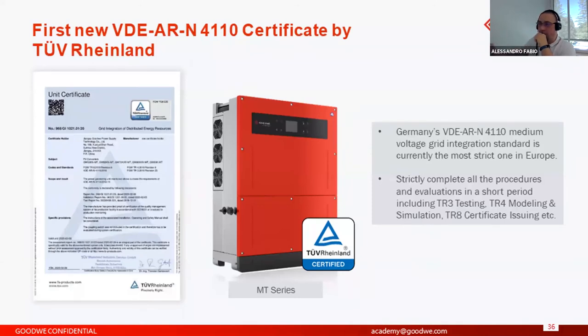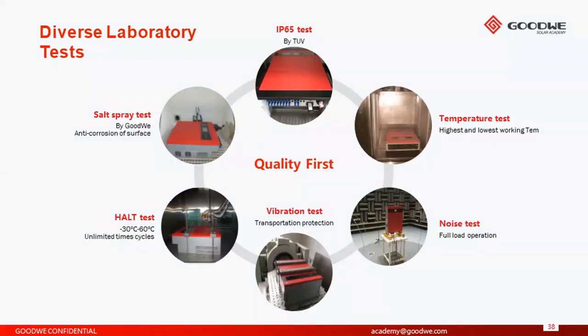So we also have certification worldwide, for example, a certificate for the German norms, the 4110 for the medium voltage, because it's a standard the German market requires. After production we have diverse laboratory tests inside. For example, the salt spray test or IP65 test for external devices. Internally we have our own tests: a temperature test, a noise test, a vibration test and also the aging test.